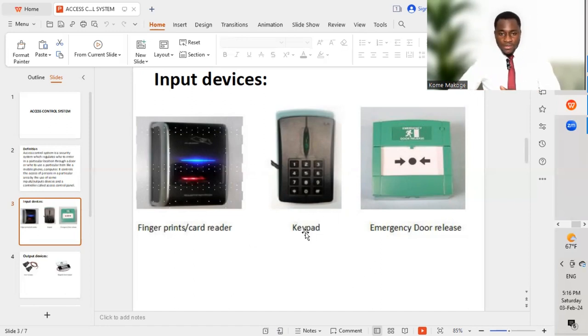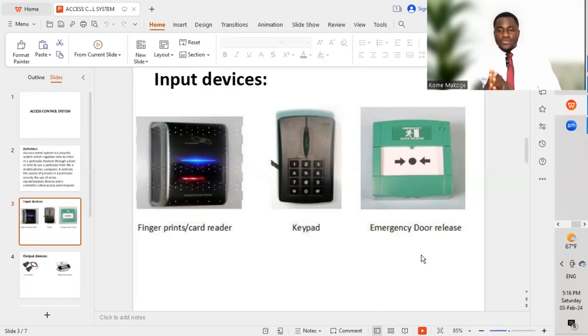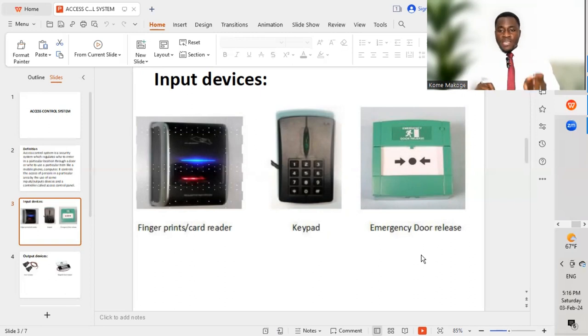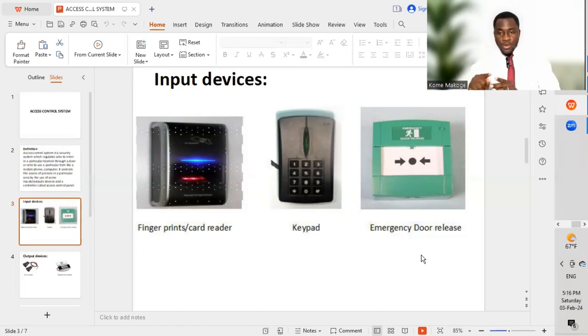The next input device is a keypad, where passwords are entered. The password is determined based on what has been programmed to the access control panel. We also have an emergency door release button, which is used strictly in emergency conditions — that is, in the case of fire. Since the fire alarm system interfaces and interconnects with the access control system, during a fire you press this push button, which sends a signal to the access control panel to open that particular door.